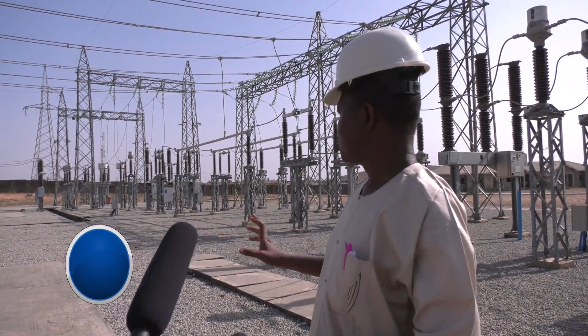Explaining further, the Assistant General Manager Transmission, Birnin Kebbi Sub-Region of TCN, Engineer Kabiru Suleiman, explained the power supply network. You can see the supply that comes from Kontagora on 132 is entering the Yauri substation. So in Yauri substation, we have the 1.5 circuit breaker arrangement. So already we have the line that is coming from Kontagora, and we have the second line that is a future line, so that we can take 132 supply to another station.